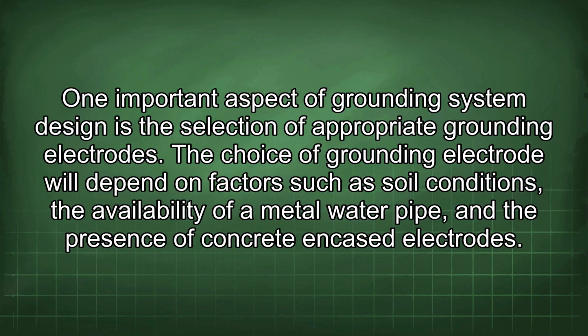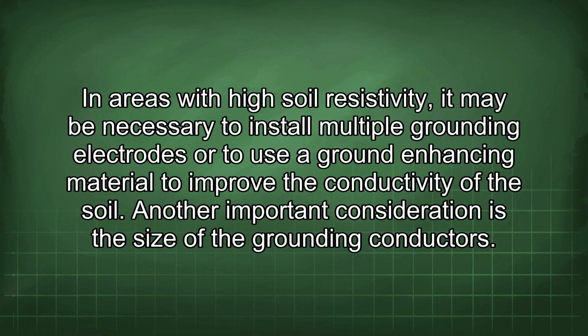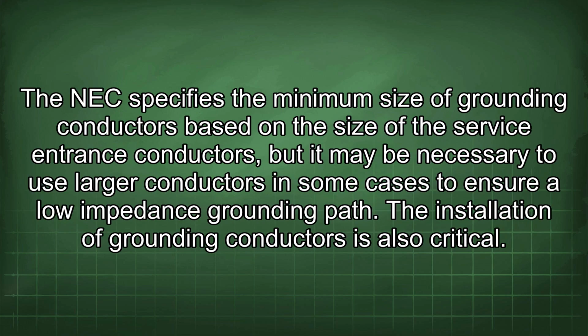One important aspect of grounding system design is the selection of appropriate grounding electrodes. Choice of grounding electrode will depend on factors such as soil conditions, the availability of a metal water pipe, and the presence of concrete encased electrodes. In areas with high soil resistivity, it may be necessary to install multiple grounding electrodes or to use a ground-enhancing material to improve the conductivity of the soil. Another important consideration is the size of the grounding conductors. The NEC specifies the minimum size of grounding conductors based on the size of the service entrance conductors, but it may be necessary to use larger conductors in some cases to ensure a low impedance grounding path.